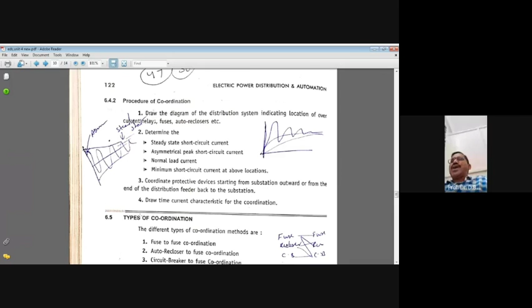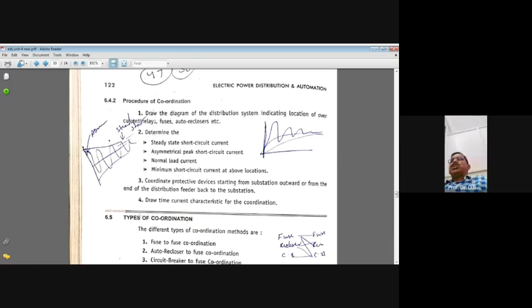Coordinate the protective devices starting from the substation onwards, from the end of the distribution feeder back to the substation. At the 33 kV substation, 33 kV is stepped down to 11 kV. 11 kV is given to your distribution transformer. The distribution transformer secondary is connected to a single phase 3-wire system or 3-phase 4-wire system, as per the customer's choice. Then draw the time current characteristics of the distribution protective devices coordination.